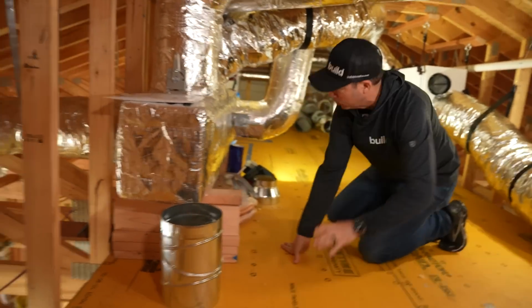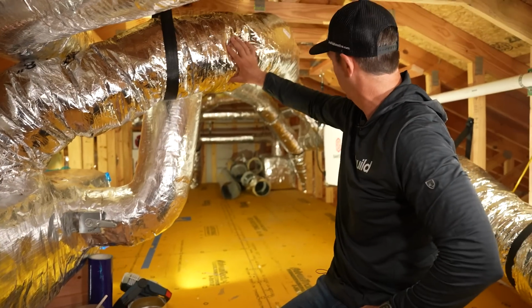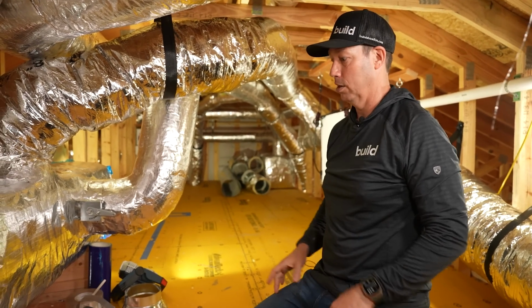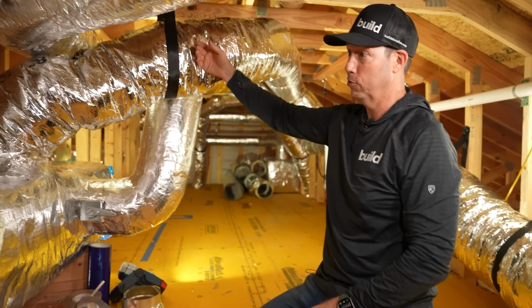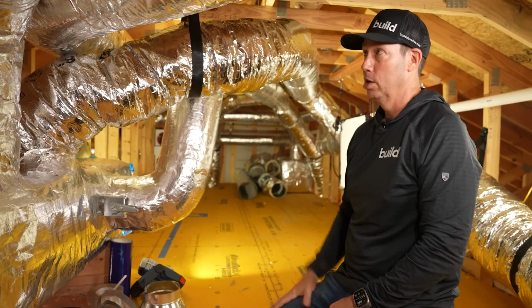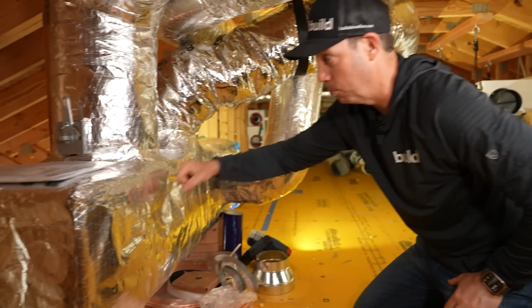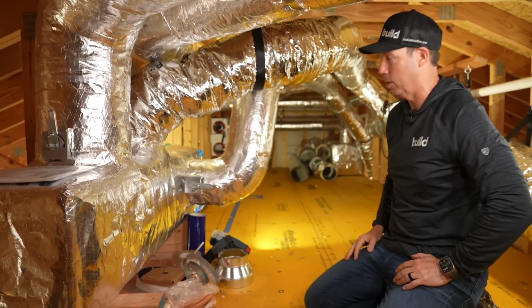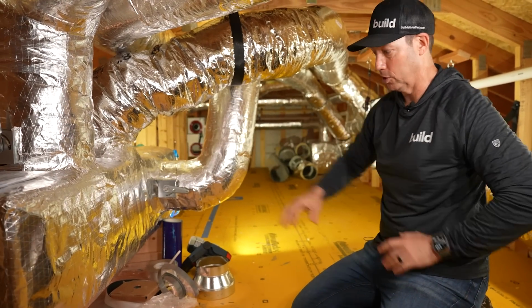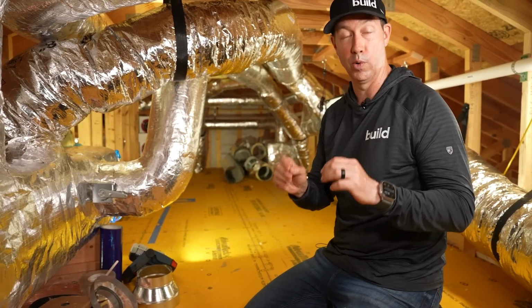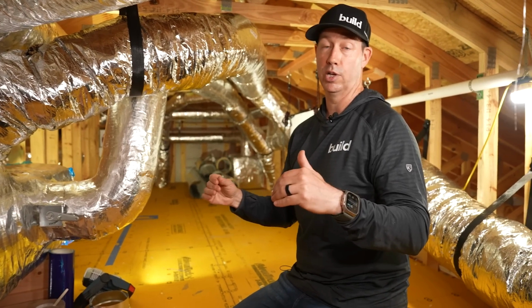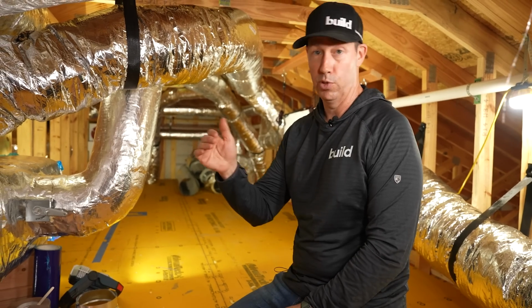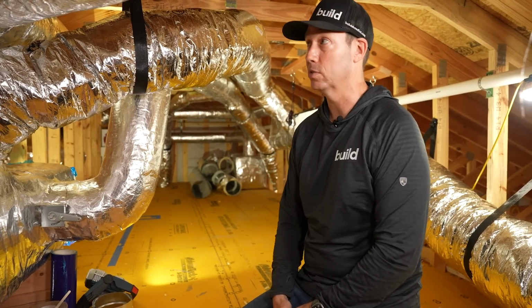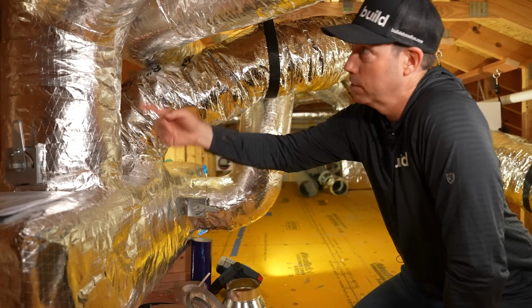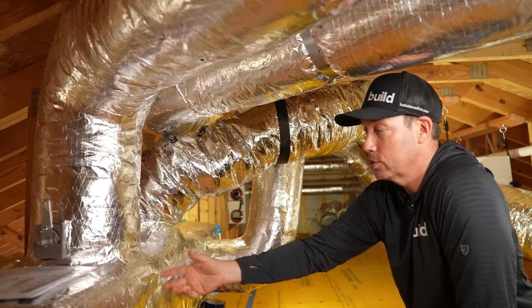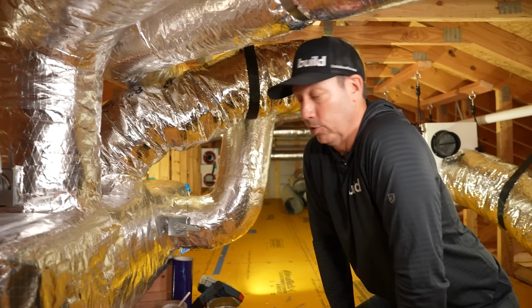This is all my traditional rigid metal trunk line. We do have a little bit of flex in the system as well. The flex will quiet the system down, and it's also frankly a lot easier and faster to run. But all the main lines you see here are metal that have been insulated on top of the metal, and what you can't see is that they've done a really nice job of mastic-ing all the joints. We're looking to make sure that when we do a duct blaster test on this, we're less than 5% loss for the system. And when you've got rigid ducts like this, like that 90-degree bend you see, that's going to be so much better than if we'd run that in flex duct.